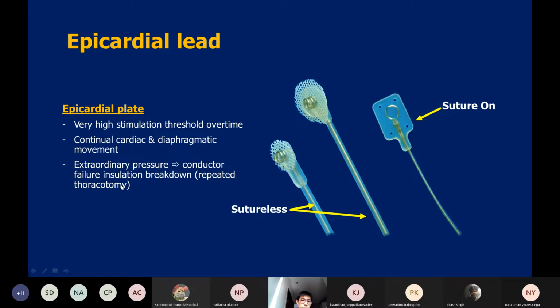And the disadvantage of the epicardial lead is that there is high movement between the heart and the leads, because it is outside, and the leads can interfere with the heart and also with the diaphragm near the implant site of the leads. This lead can also break down easily, because the pressure of the thoracic cage outside the heart is higher than the pressure inside the heart chamber. And this leads to easy conductor failure and insulator breakdown.